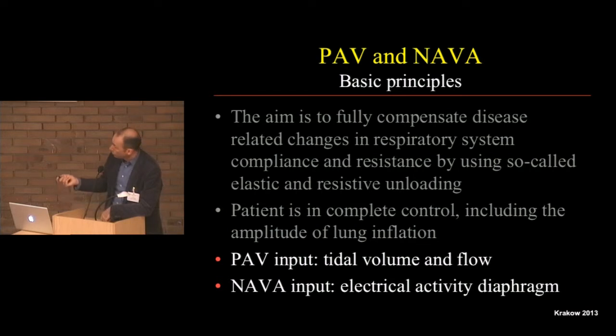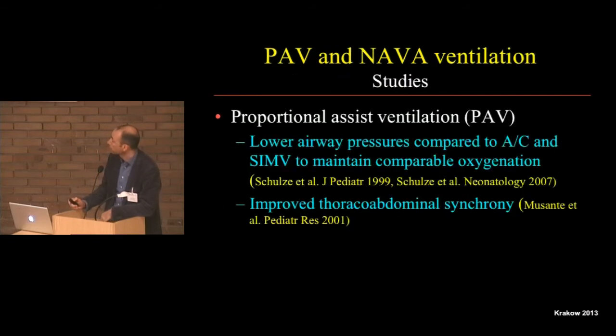And proportional assist uses the tidal volume and the flow to assess how much support a baby wants, and NAVA uses the electrical activity of the diaphragm. If the baby takes a big breath, it means there's a lot of electrical activity, so the machine will give a big support. If the baby takes a small breath, there will be less activity, and the machine will give a small support during the inspiration.